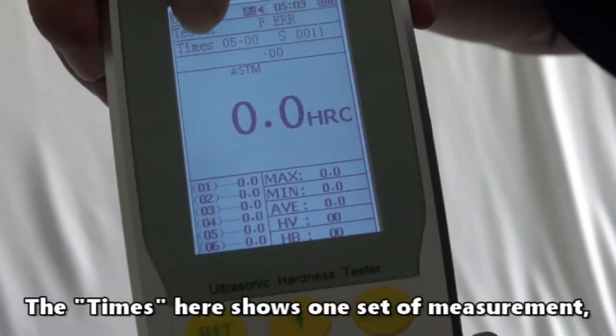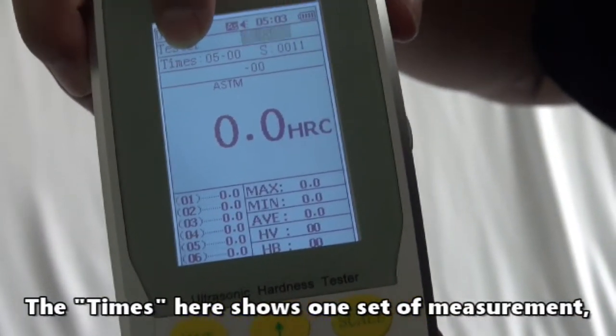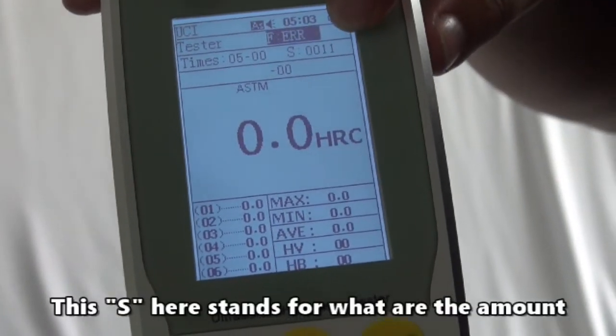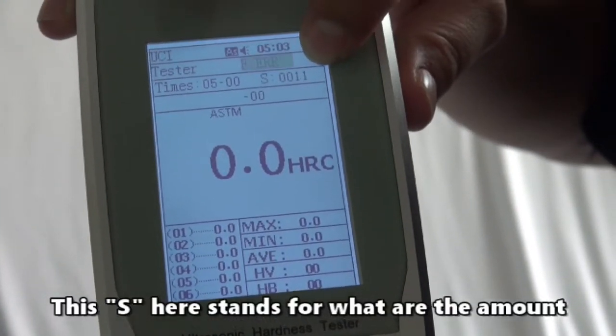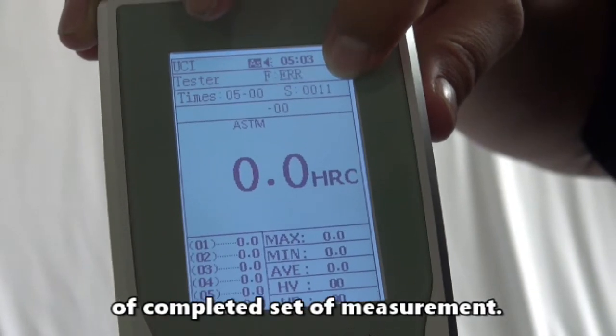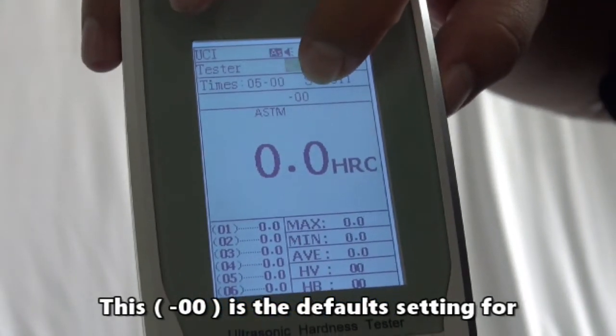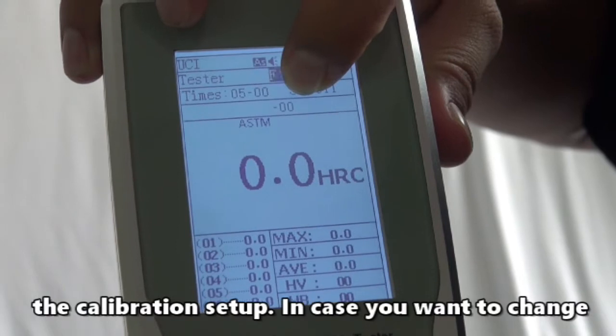This F shows the force applied from the motorized probe. The times here show one set of measurement. This S stands for the number of completed sets of measurement. This 00 is the default setting for the calibration setup.